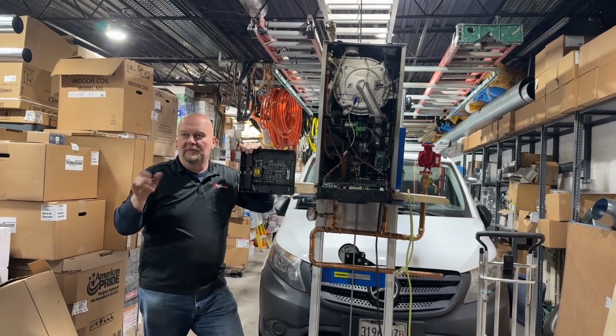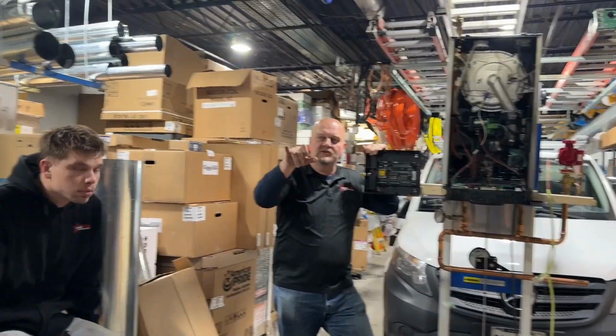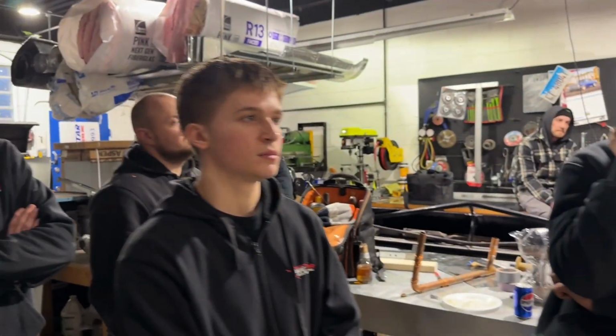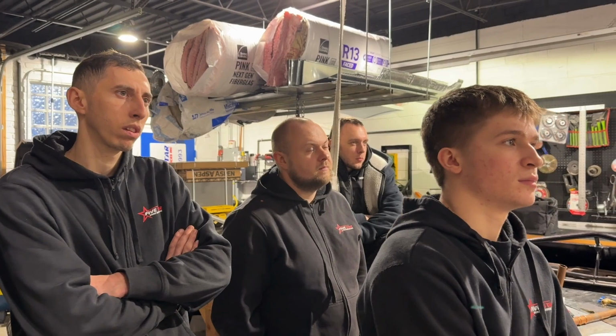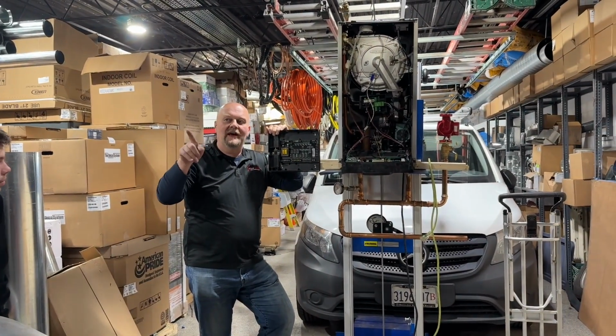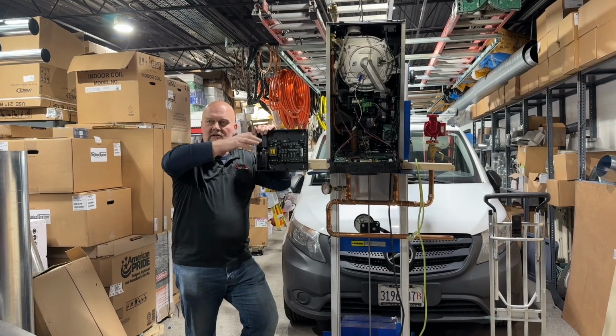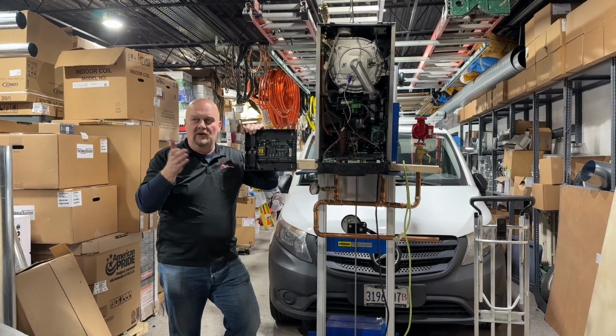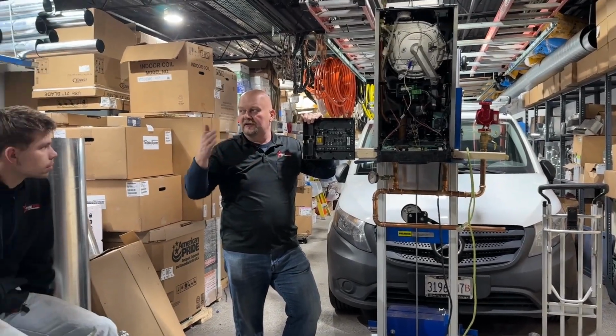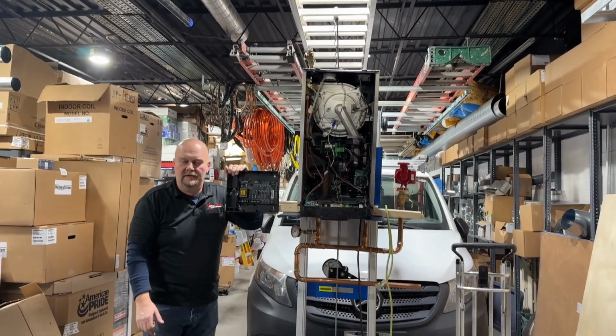And by the way, Vasa, you should check on yours to make sure you don't have to set up for primary too, because you might on the zone panel that you have. And you don't want it to happen, because what's going to happen then is you're going to have 3 air handlers trying to work, and only one of them will be working until the temperature is satisfied over there. I'll explain it to you in Polish if you want to hear it.